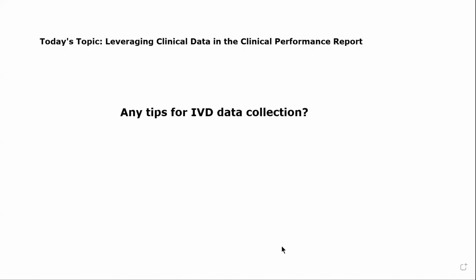Organization is critical. Start with the guidelines. See if there are any guidelines specifically pertaining to the accuracy of testing. Identify what your alternative ways of making that clinical diagnosis are. If your test is not available to a person, how would they make that same diagnosis? And then accurately identify your competitors, finding competitor devices that have the most similar characteristics to your device.